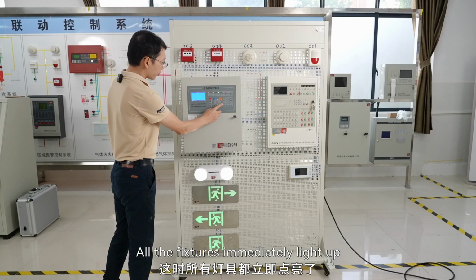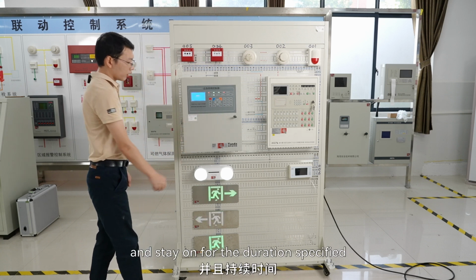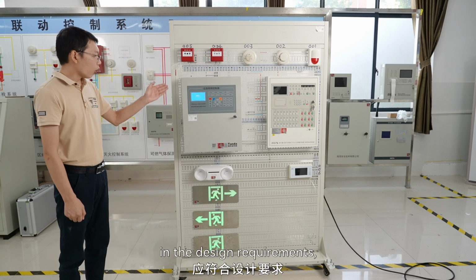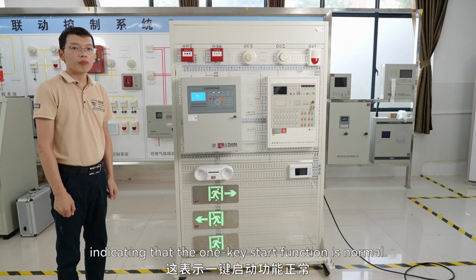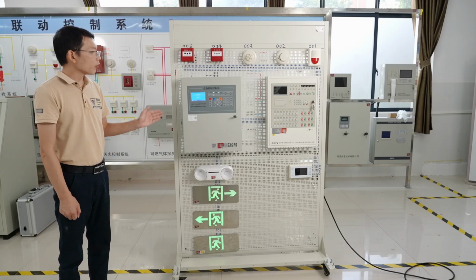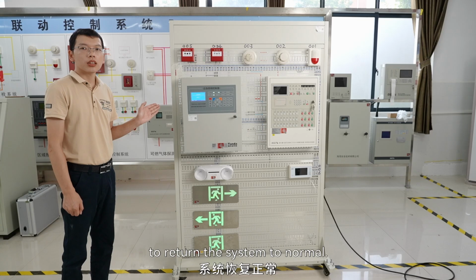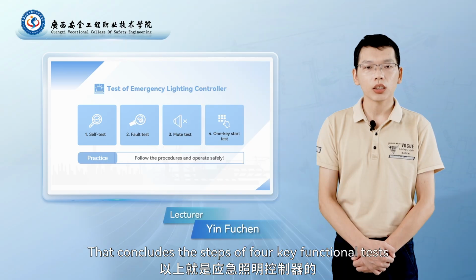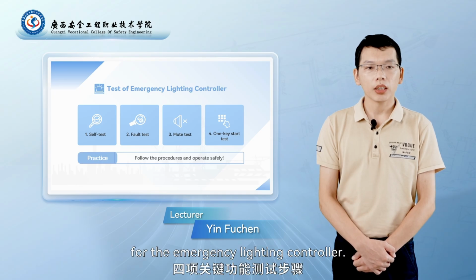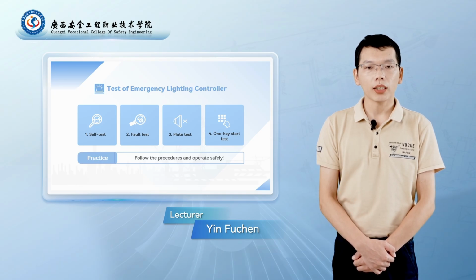All the fixtures immediately light up and stay on for the duration specified in the design requirements, indicating that the one-key start function is normal. Press the reset button to return the system to normal. That concludes the steps of four key functional tests for the emergency lighting controller.